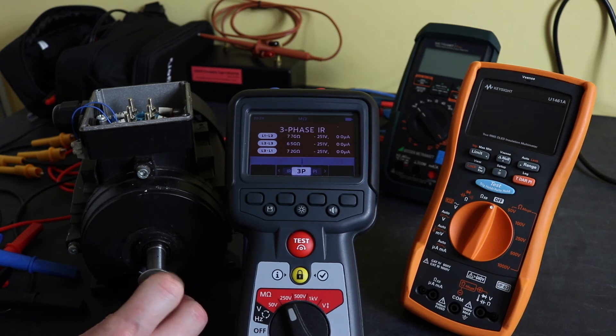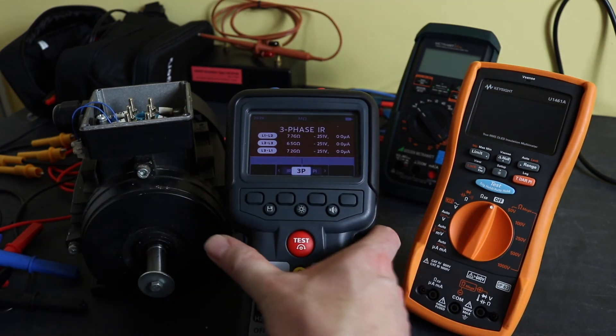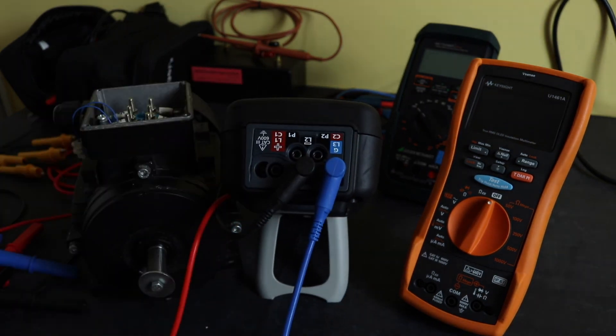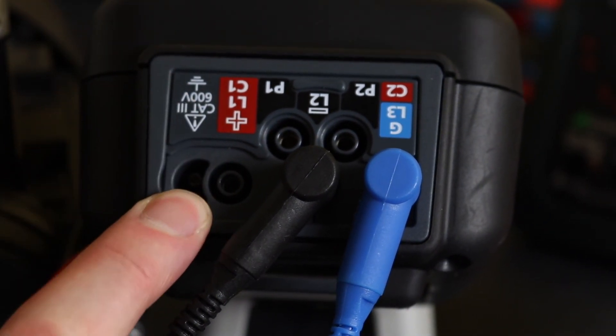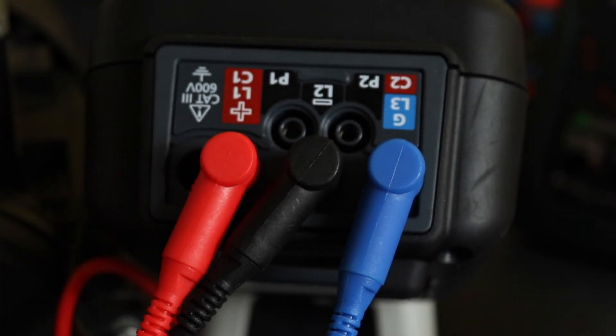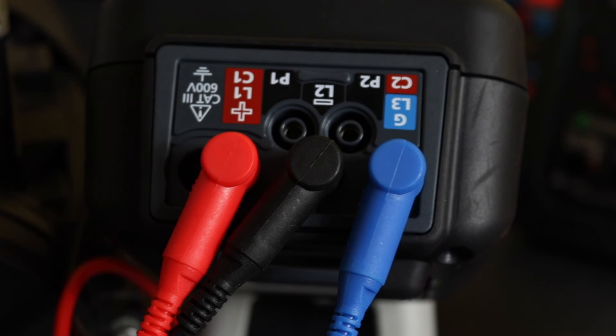My downside, or my thoughts to this on the downside of this, although I do phase to phase test, that's fine. I also do a phase to earth test. So for me, it would have been nice if Megger, instead of using this connection here, zoom in, so they have this connection here for a remote probe function. I don't find that very useful for a motor. What I would prefer to have seen is that to be a fourth terminal for this test. So I could have had the three connected up to the winding, and then taken this one onto the motor case. So I could then have done a phase to phase test, and then each phase to earth as a second part of the test, which is what you would do anyway.